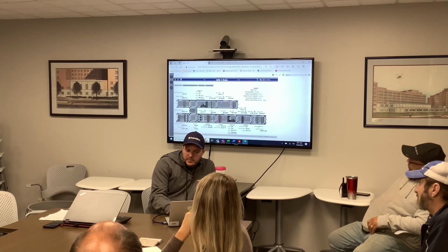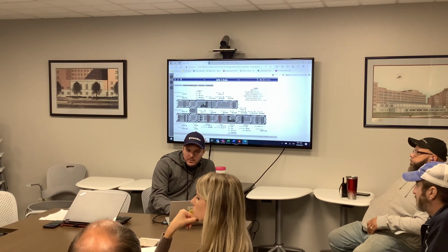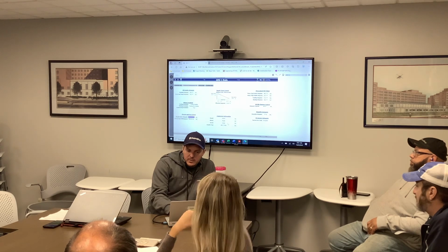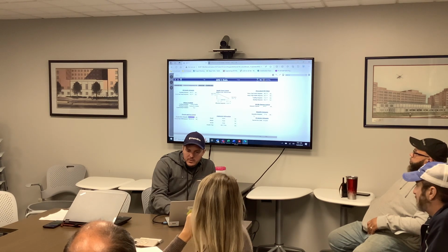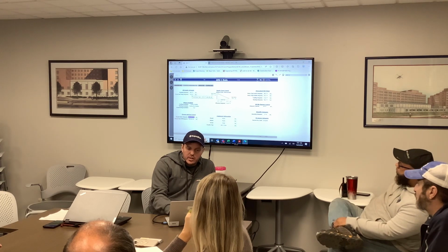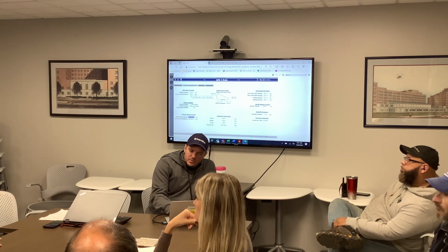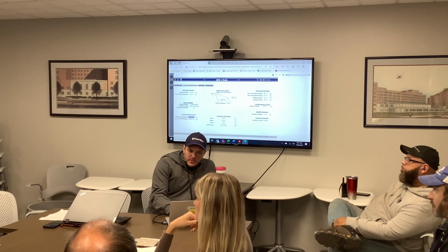Gotcha. You have the economizer programming in there anywhere, and is it showing on the set points? No, just the econ low. It doesn't have a switch over, it only has the econ low set point. So it'll start driving below minimum position if your mixed air hits 45 or lower. Now, are those numbers drawn off of enthalpy, or is it just like a default number? That's dry bulb.